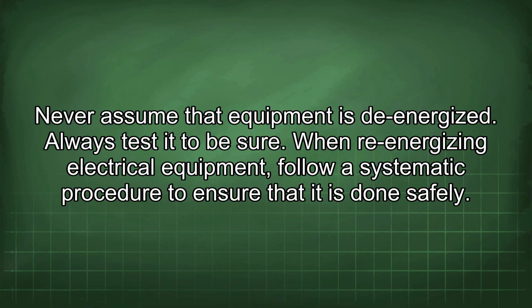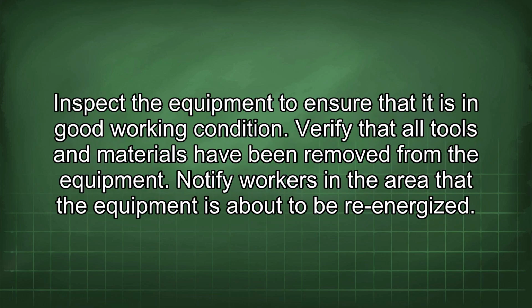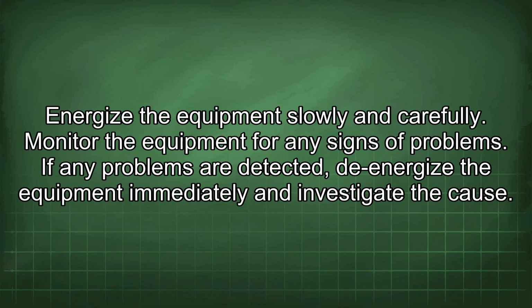When re-energizing electrical equipment, follow a systematic procedure to ensure that it is done safely. Inspect the equipment to ensure that it is in good working condition. Verify that all tools and materials have been removed from the equipment. Notify workers in the area that the equipment is about to be re-energized. Energize the equipment slowly and carefully. Monitor the equipment for any signs of problems. If any problems are detected, de-energize the equipment immediately and investigate the cause.